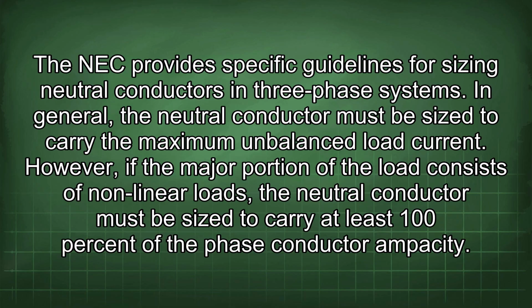In general, the neutral conductor must be sized to carry the maximum unbalanced load current. However, if the major portion of the load consists of nonlinear loads, the neutral conductor must be sized to carry at least 100% of the phase conductor ampacity.